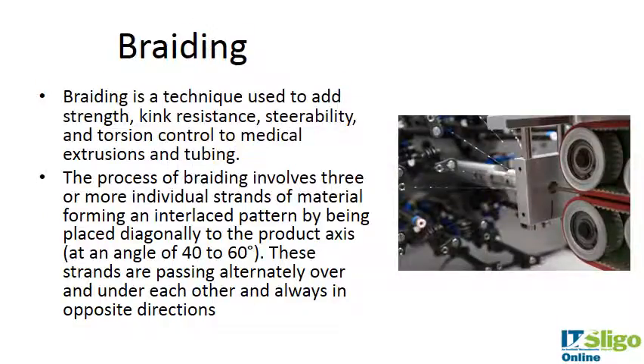Braiding is the other technique I want to look at. As the name suggests, it's like braiding or plaiting hair, as we used to do as children. Braiding adds strength, kink resistance, and steerability to medical extrusions and tubing, and it gives good torsion control — meaning it gives the surgeon good control over the bendability of a catheter, for example a coronary catheter.